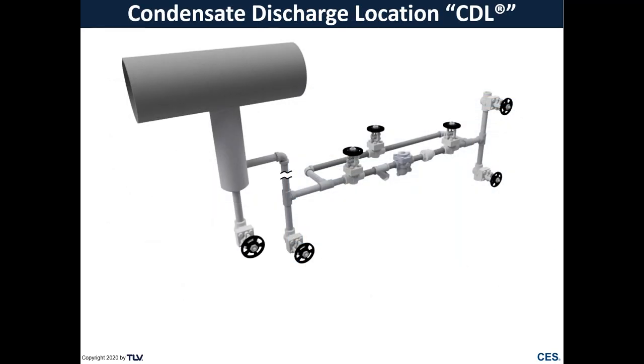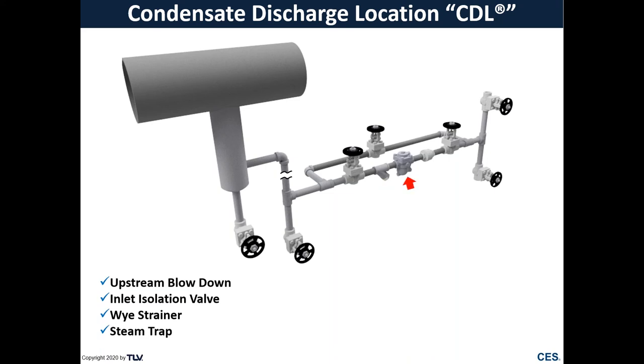Now, our condensate discharge location, you can see here, there are many different components. And this is what we would consider an ideal condensate discharge location, but the condensate discharge locations at your site may look a little bit different depending on what your site specifications are. So you may see all or maybe only a portion of these components. So first is going to be an upstream blowdown valve, followed by an inlet isolation valve. Next, we have a Y strainer, which is helping protect that steam trap from dirt and debris and preventing that steam trap from being blocked, which can cause condensate backup. Of course, we have our steam trap, as well as a bypass valve.